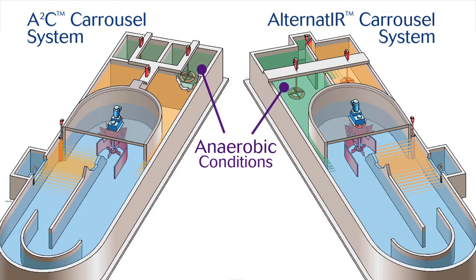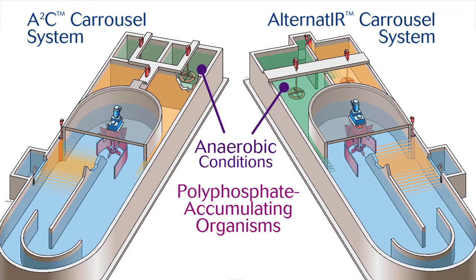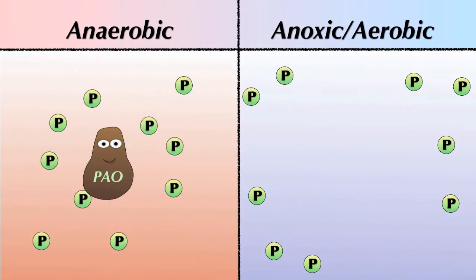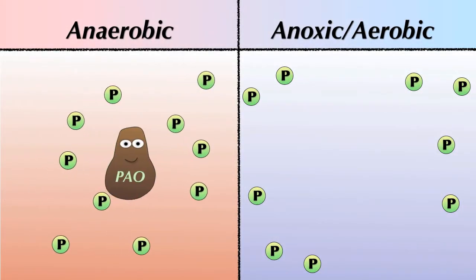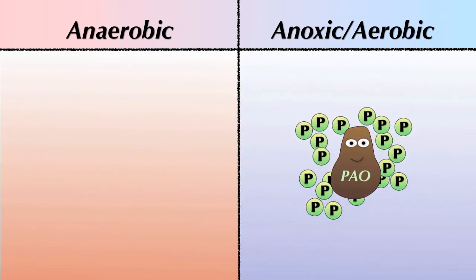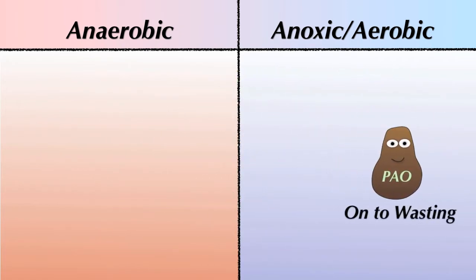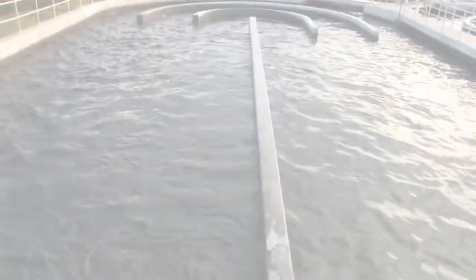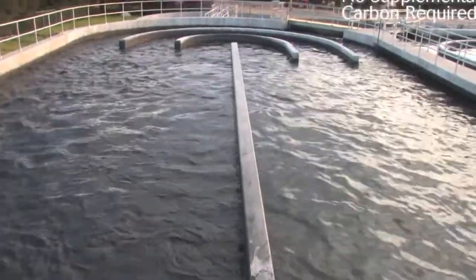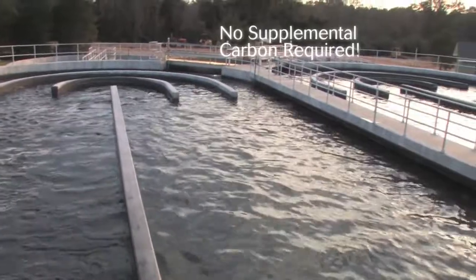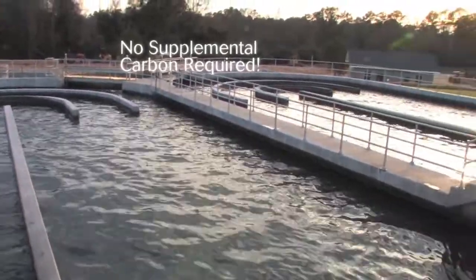By including an anaerobic zone, polyphosphate accumulating organisms, or PAOs, are allowed to thrive. When properly cultivated in the carousel system, these specialists are capable of reducing phosphorus concentrations in the effluent. An optimized BNR carousel process will typically perform all of these functions without the need for supplemental carbon addition.